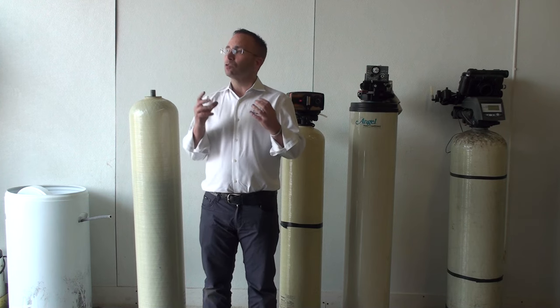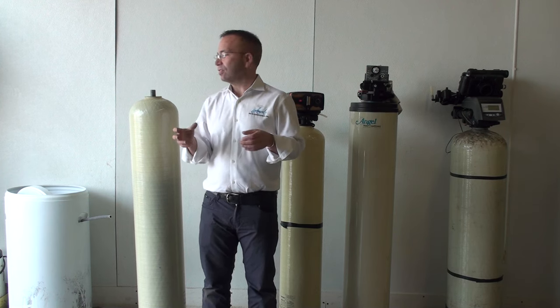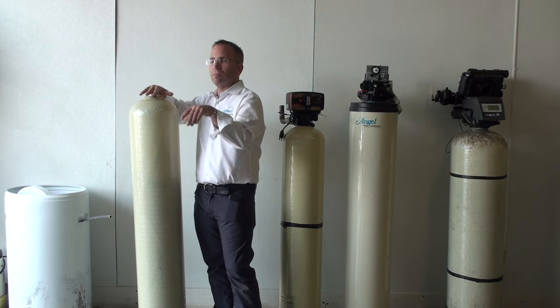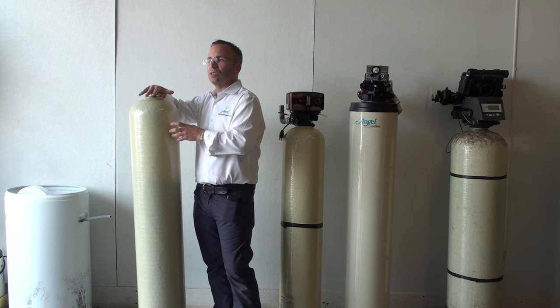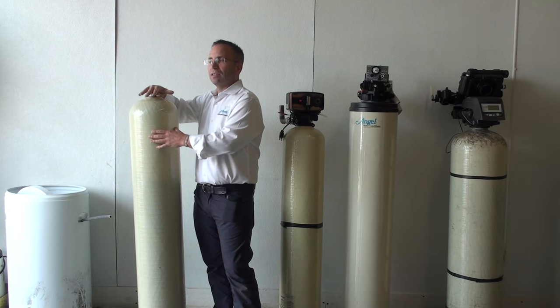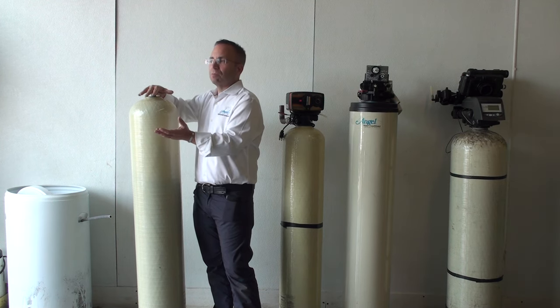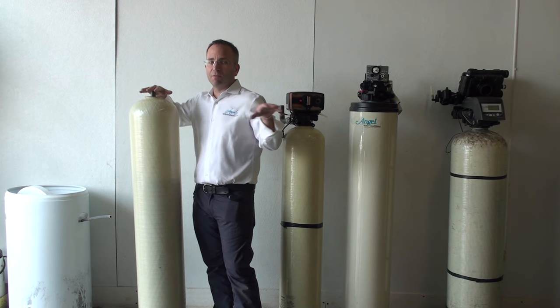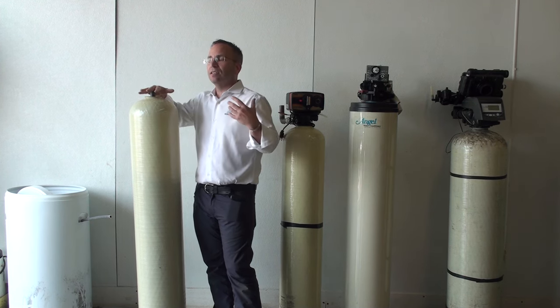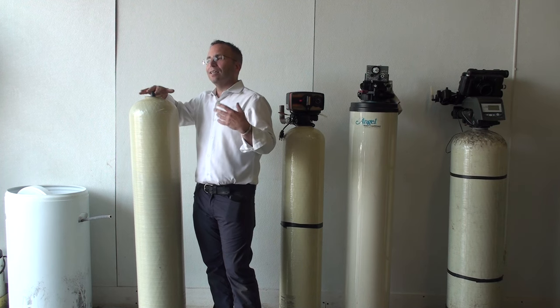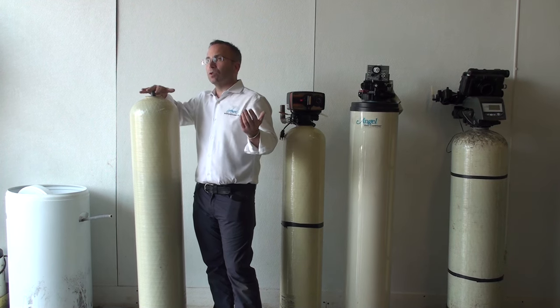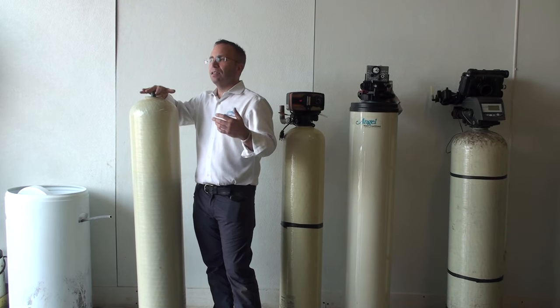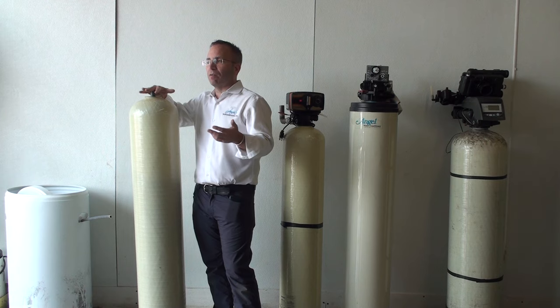The way they started is water softeners were exchange tanks. It was an in-out head, and what they would do is they would have a service come by your house, and you'd exchange the tank out and put in a new tank every month. Sometimes every week, depending on how hard you want it. We know that the average water softener that we design, we size up, we want it to regenerate no earlier than every three days. So we really don't want it to go every other day. In fact, the little bit longer we can go, the better off you have it.